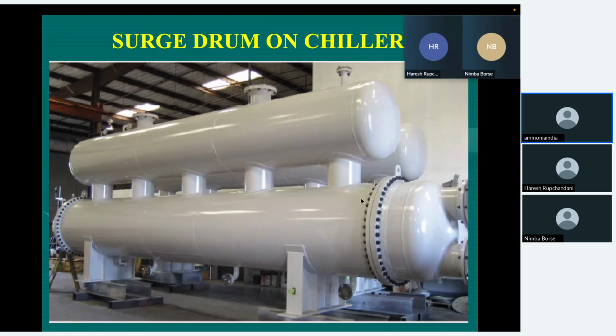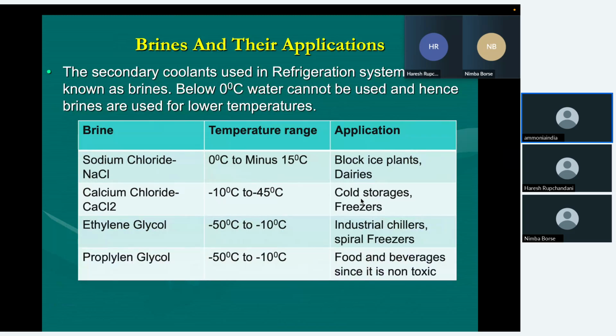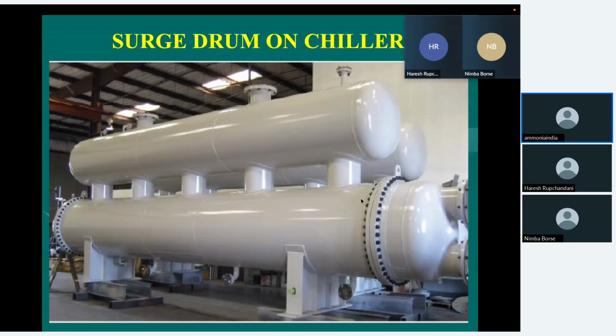And the last is liquid coming in the form of mist. If mist is coming to the compressor, it is also liquid, and that will damage your valve plate. There will be etching on the valve plate. If you see the valve plate, there will be etching on it. So this is how liquid comes to the compressor, not only in liquid form. It can come in these various forms, and we need to avoid all of them. Therefore, the velocity to be maintained in the surge drum is very, very important. The velocity should not be more than 50 to 75 feet per minute. So design these pipelines for this velocity, and you will never have a problem of compressor breakdown.